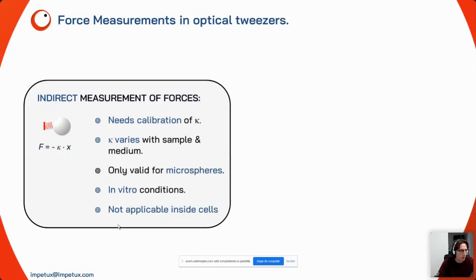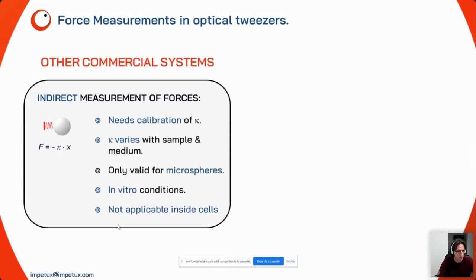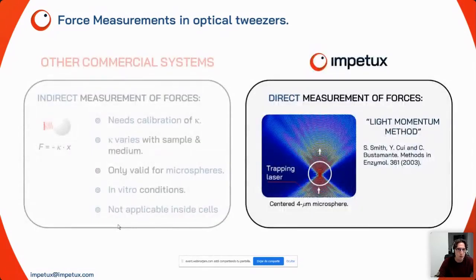Some problems arise because the trap stiffness kappa varies depending on the sample and medium conditions, so if you change experimental conditions you need to recalibrate. Furthermore, this indirect method is only valid for spherical objects and is basically limited to in vitro conditions — it cannot be applied inside complex media like cells or tissues. This is what other commercial systems do to measure forces, but we use a different approach: a direct method called the light momentum method.